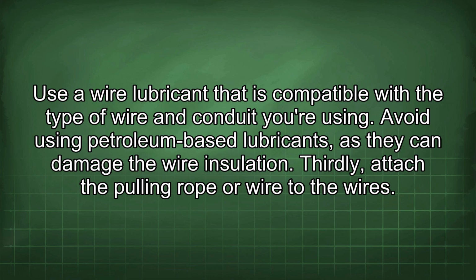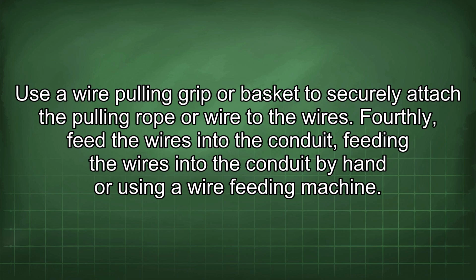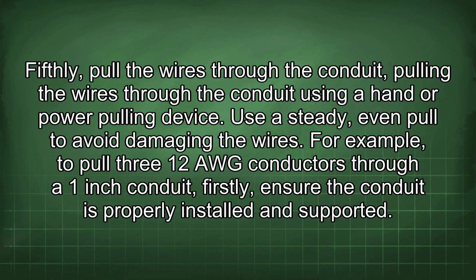Thirdly, attach the pulling rope or wire to the wires. Use a wire pulling grip or basket to securely attach the pulling rope or wire to the wires. Fourthly, feed the wires into the conduit, feeding the wires into the conduit by hand or using a wire feeding machine. Fifthly, pull the wires through the conduit, pulling the wires through the conduit using a hand or power pulling device. Use a steady, even pull to avoid damaging the wires.